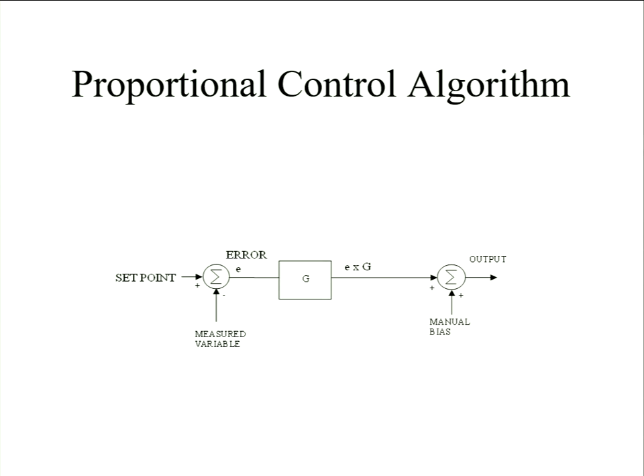Alternatively, sometimes it's described as proportional band. I must admit, in my days, I never really tended to think of it as proportional band. I much preferred to think of it as gain, and particularly like gain in so many million cubic meters per percent of valve movement, because then I could understand what the process was. But what this does, I suppose, in some way, is normalise the way you'd think about all controllers.